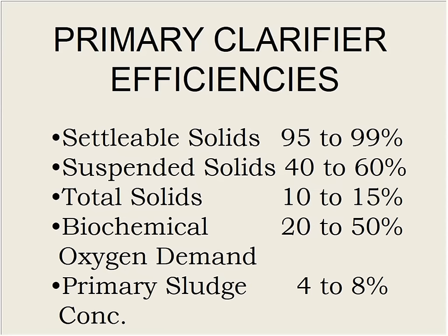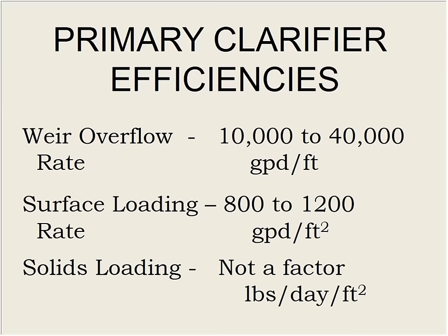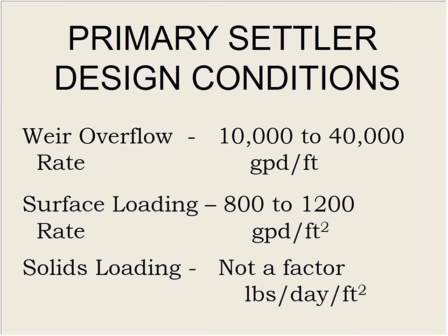But at the end of the day, if all has gone well, we've removed 95 to 99% of settleable solids and all of the floatables. We've lost a little bit of total solids, some of our suspended solids. Our BOD has been reduced. I wouldn't go to 50%, but 20 to 30 probably. And we've got a sludge that, depending on how fast we withdraw, might be 4% or so, which is pretty decent.